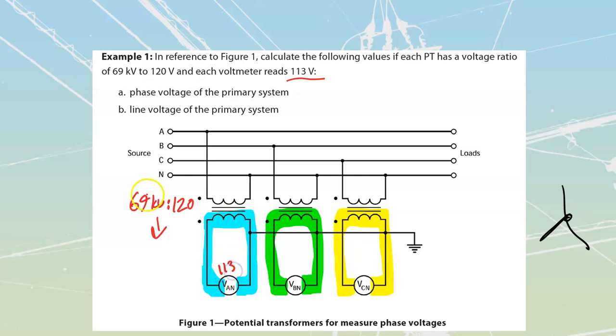Which means that by default, I don't even have to do a calculation before I know that we're going to have a value that's less than 69 kV on my primary. Well, how much less? We can't just go guessing when it comes to instrumentation. Let's go and calculate this out.